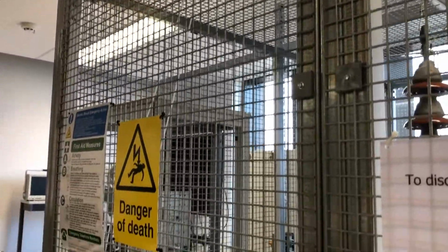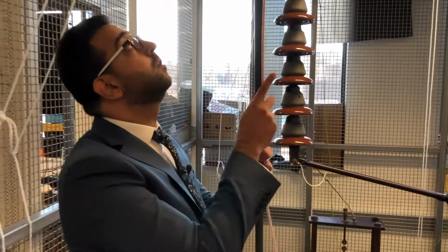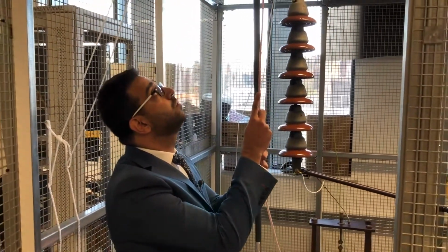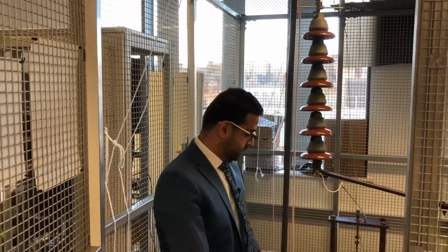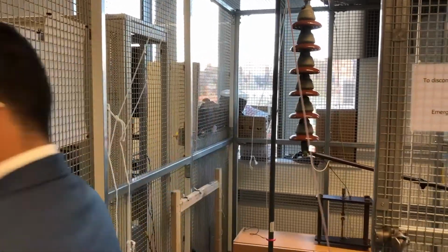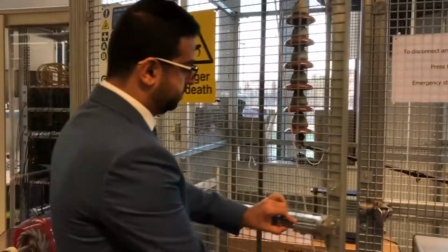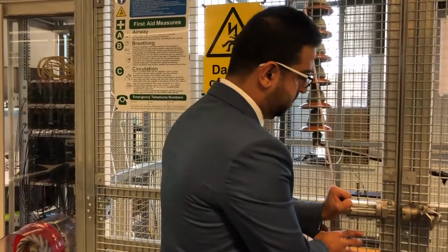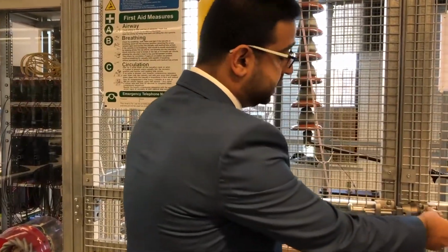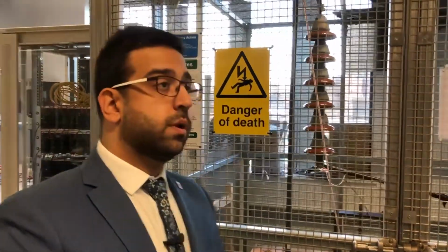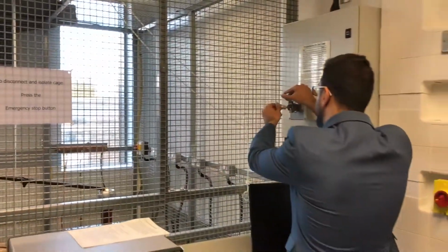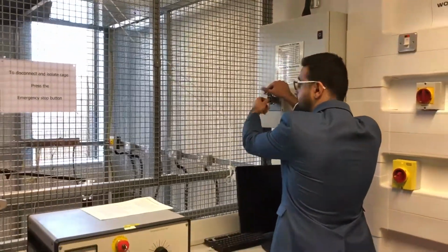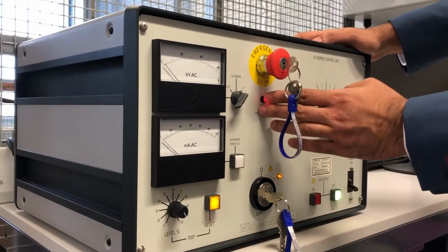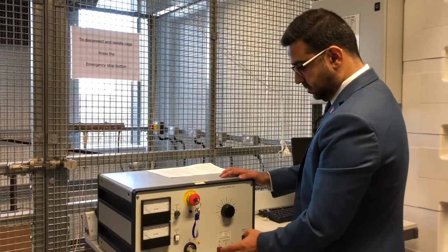Now we need to unearth the transformer and connect the earth back to the cage. The system has a lock mechanism where it won't allow operation until everything's secure. We're going to reset the system in order to do the test.